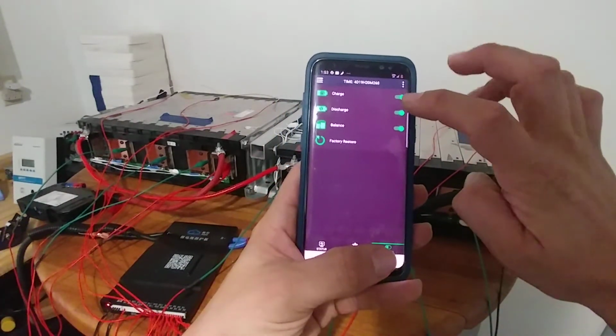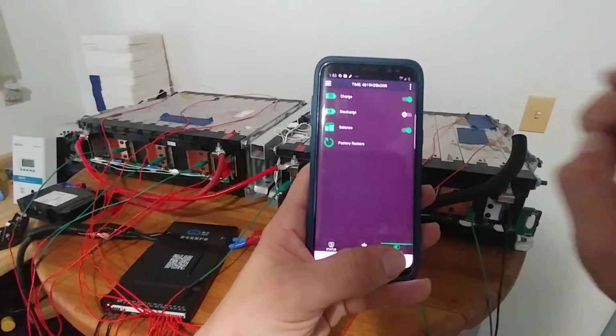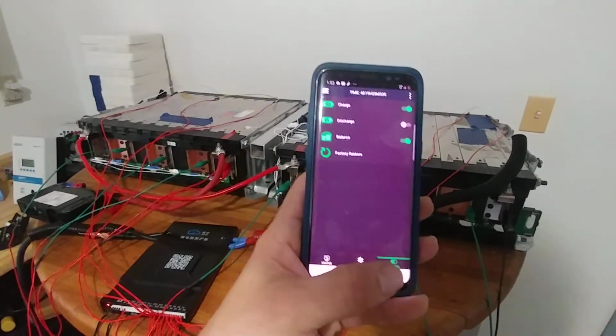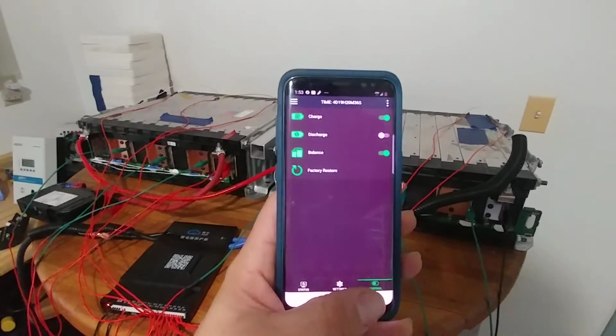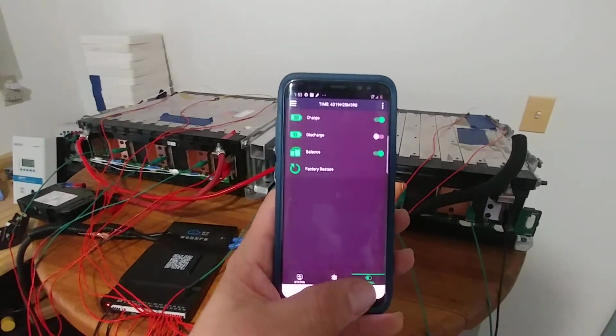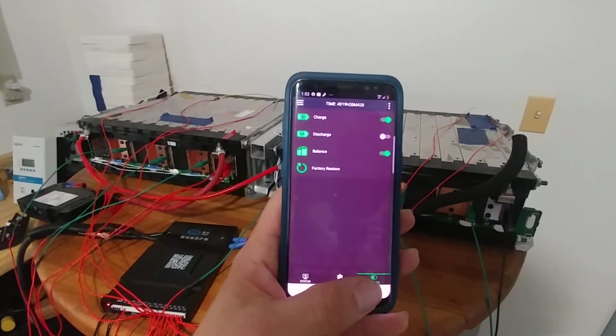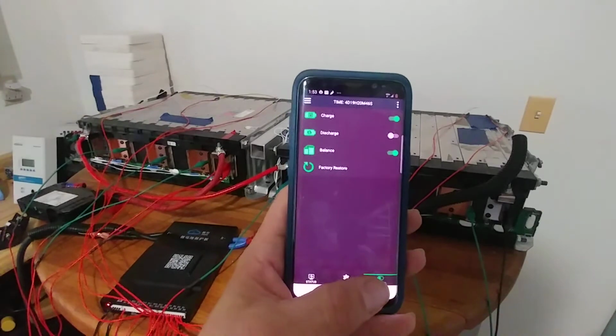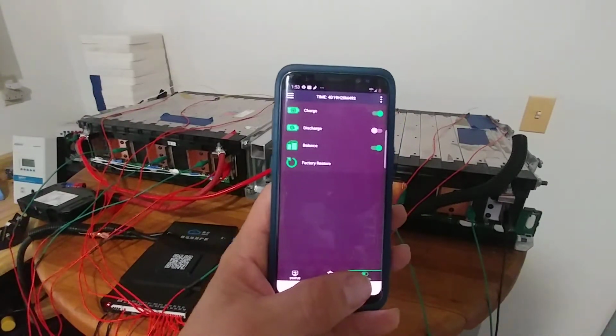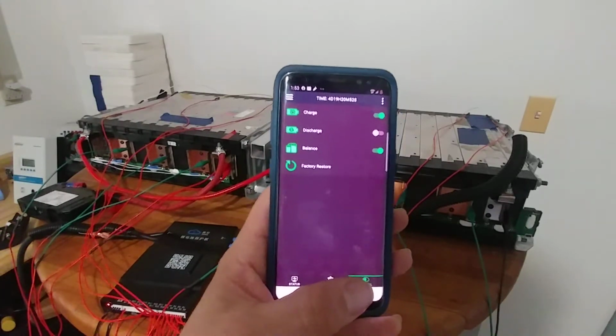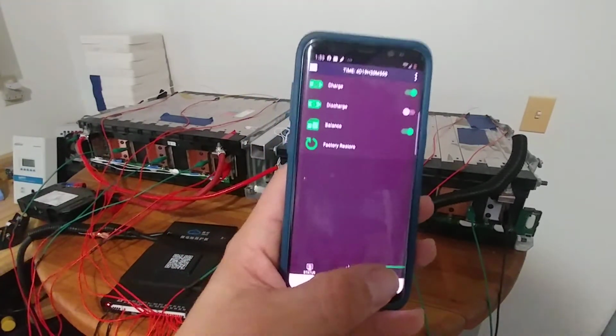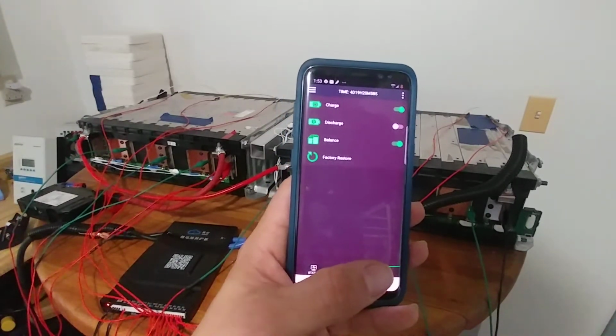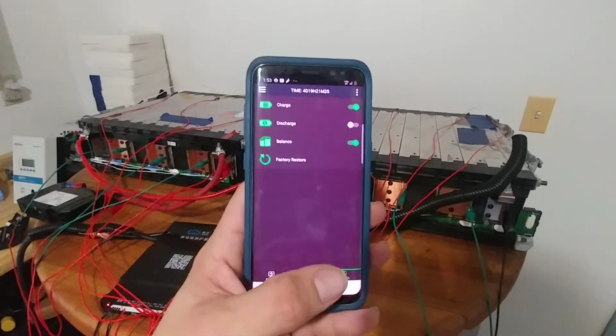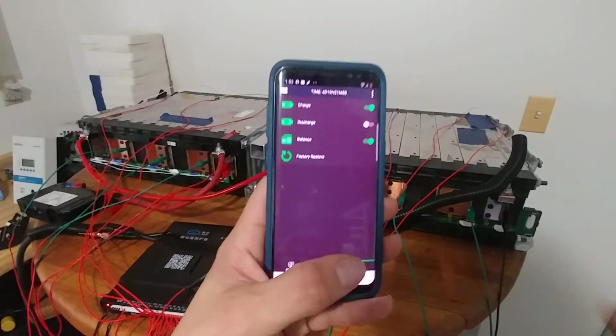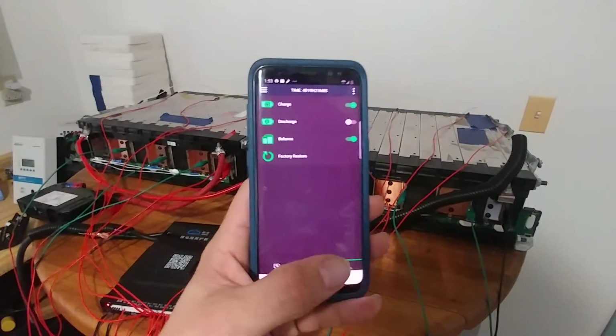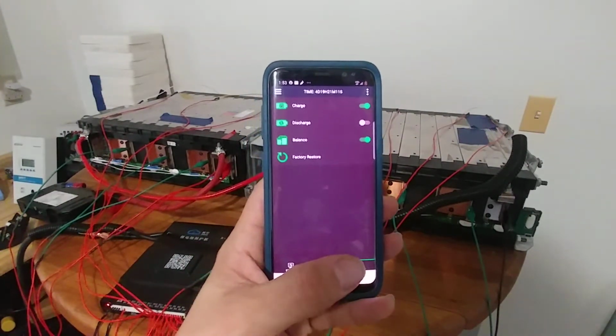So we can go ahead and actually, I believe if we cut discharge, the whole thing will shut off. No, the entire thing does stay on, but this is actually just a factor of my inverter because we're currently plugged into shore power with the battery disconnected, which is what would happen during a very high discharge or charging cycle. Let's assume you're rapid charging it and maybe the vent fan hole is blocked or something and it's just not getting enough airflow. It'll actually stop the discharge process, but everything will stay functioning. Like the inverter is still running right now because I'm not pulling enough of a load on it that actually requires a discharge from the battery, so it'll stay running.